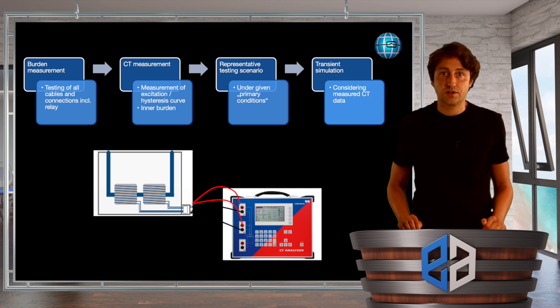What we can do however is with a portable test device we can measure the parameters individually. So firstly we may perform a burden measurement and testing all cable connections including the relay.